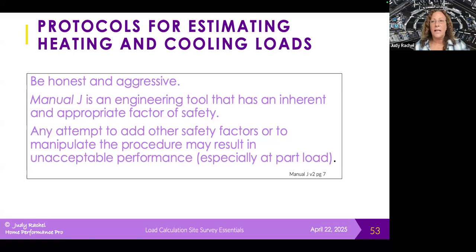for example, the sensible heat equation has a constant in it. And I talked about that earlier, in that there's that correction factor for altitude from that constant. That constant is the specific heat carrying capacity of air at different altitudes. So as the air density gets less, then that specific heat carrying capacity of air changes. Now, when I'm doing a delivered capacity test, say for a heating and cooling system, when I'm doing performance testing, I use 1.08 as the constant.